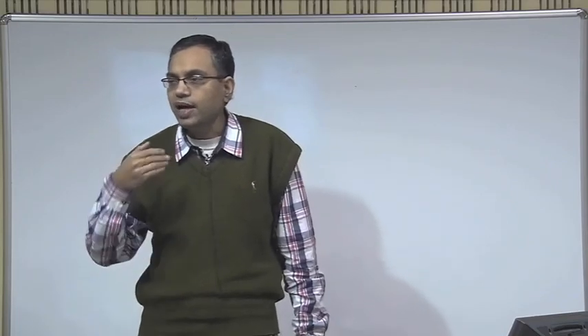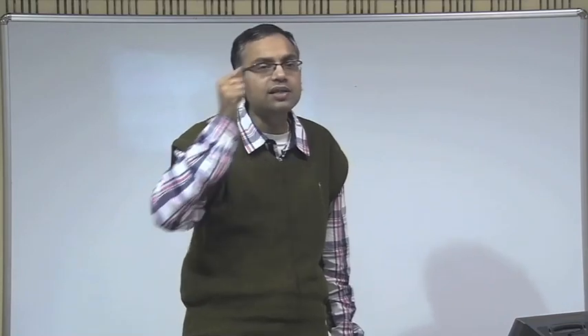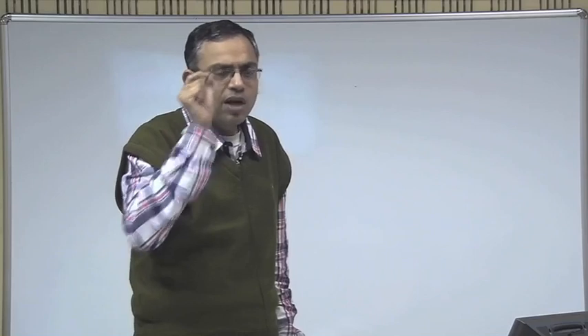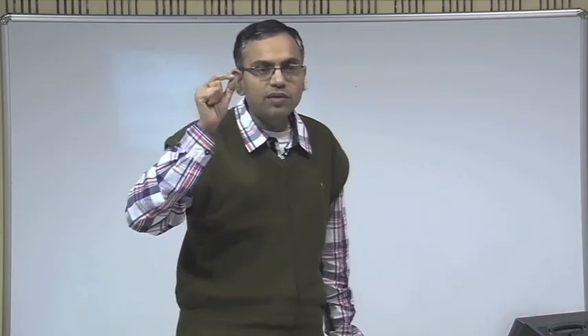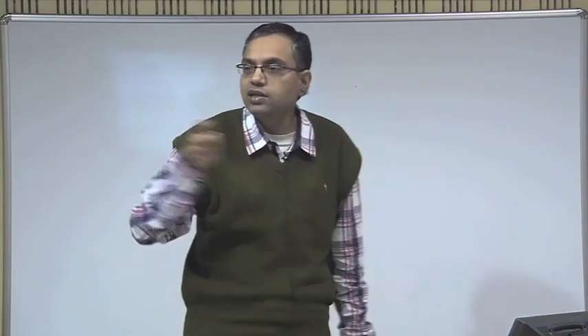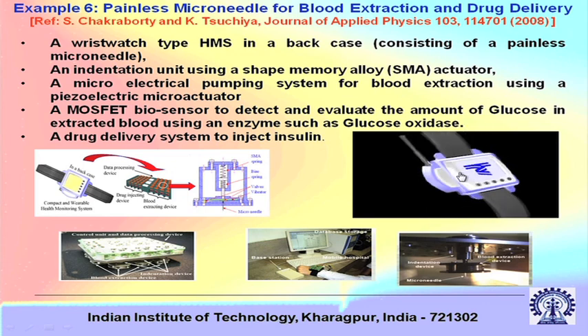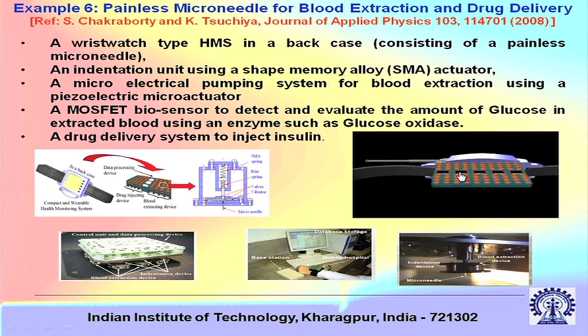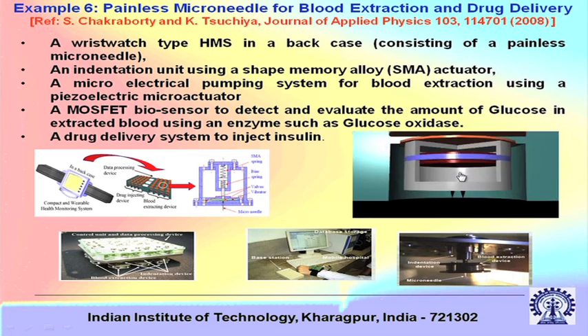If you can emulate that through an engineering device which can create a suction pressure in a miniaturized environment, then by suction pressure the blood is sucked into the needle — a small amount of blood, but good enough to make the test. Next question: when the blood is sucked, how will it be transported through the needle? Because it is a micro needle with micrometer dimensions, surface tension is a very important force. By surface tension-driven flow, blood is transmitted from one end of the needle to the other.